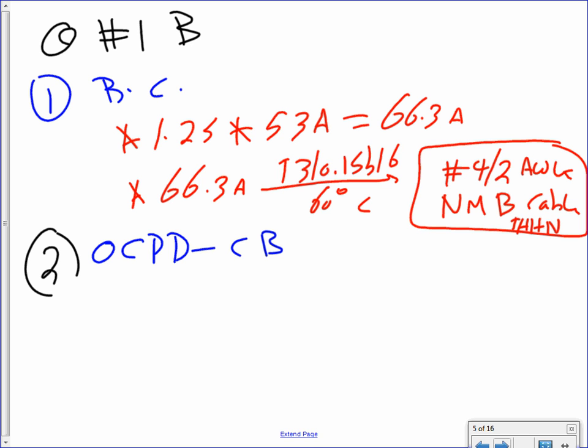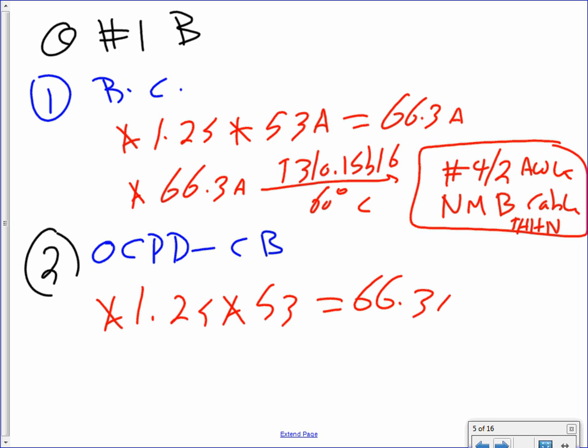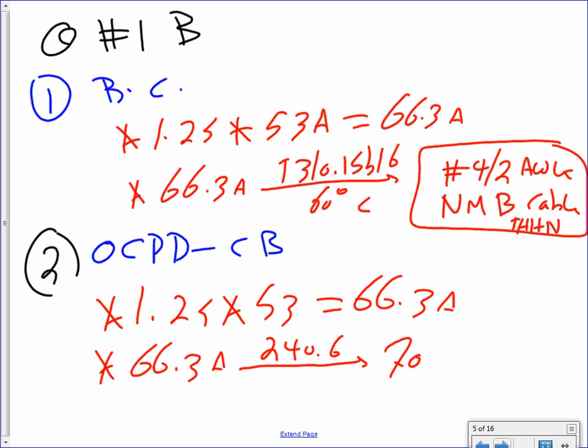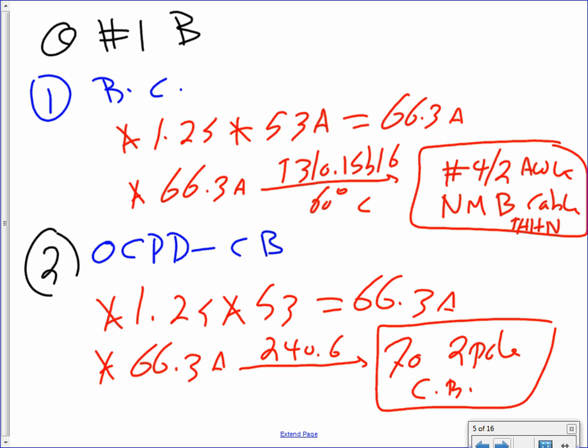Okay. Second, let's go to the overcurrent protection device, same size, 1.25 multiplied by 53, gets you 66.3 amps. Now where are you going to go? 66.3 amps, take it all the way to 240.6. That will get you a healthy 70 amp, 2-pole circuit breaker. 70 amp 2-pole circuit breaker, done.